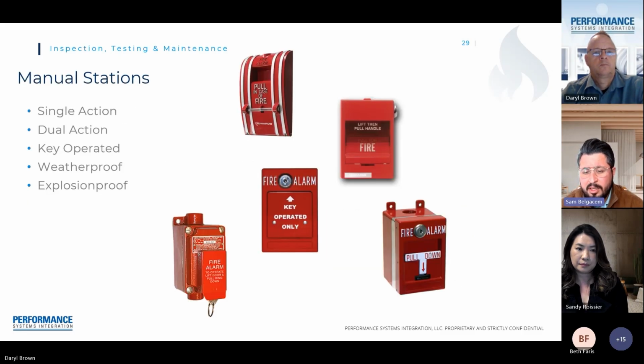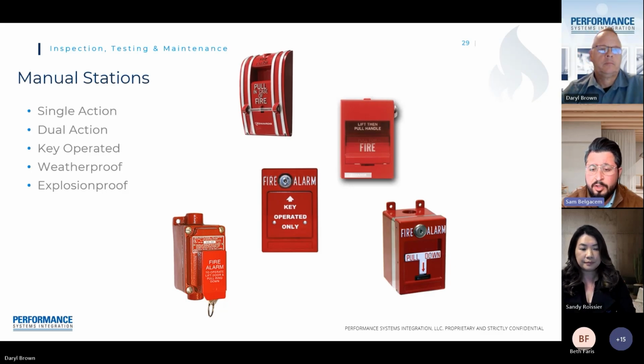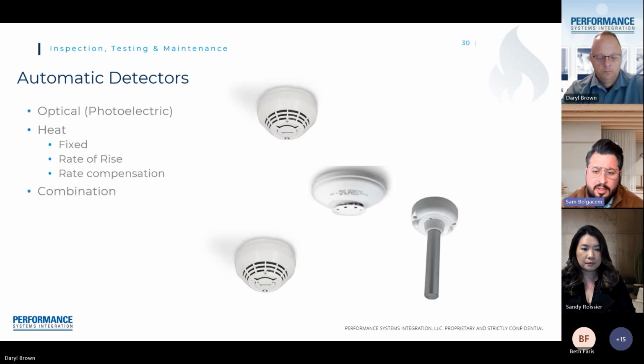Also, there is a manual device like the pull station, and it has different styles. It depends on the requirement or the environment. As you see here in the pictures, there are 5 types: the single action, the dual action, the key operated, the weatherproof, and the explosion proof. The electronic devices are also different. There is a smoke detector, a heat detector, or they can be a combination of both smoke and heat detector together. And there are different types. Also, it depends on the requirement or the environment.